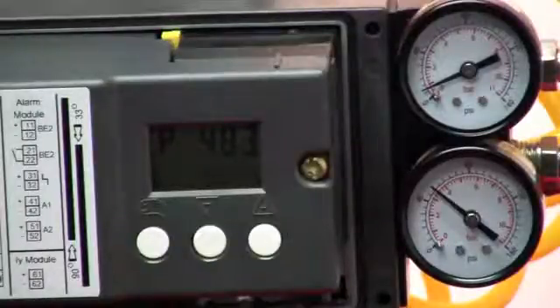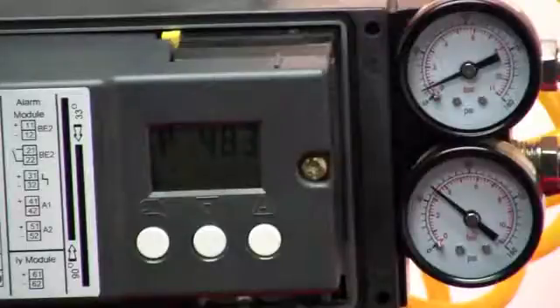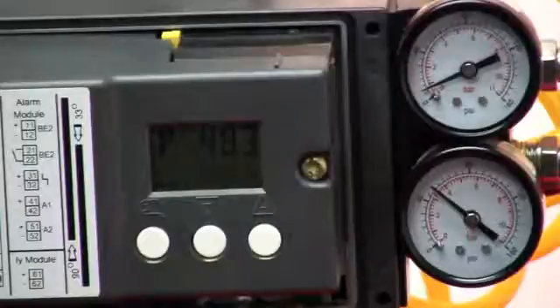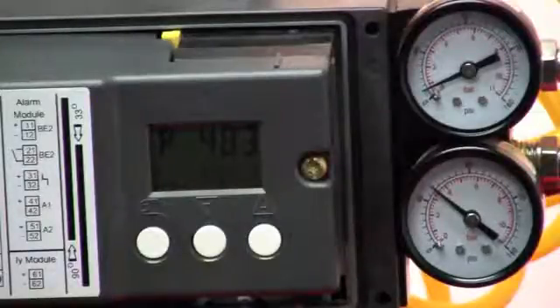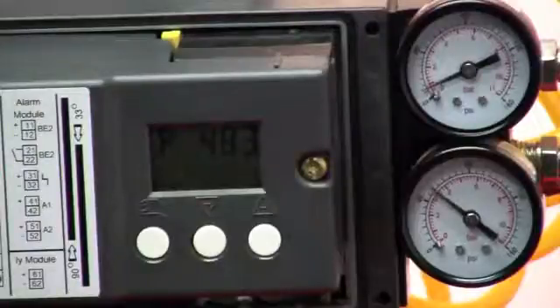Run three measures the actuating time and includes a small duration of time where the positioner does nothing except look at the leakage in the tubing going to and from the actuator and the positioner and reports this leakage to you in terms of percent of stroke per minute.